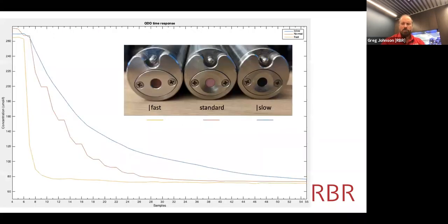Here is the photograph of the 3 foils. You can see in the center that opaque pink foil. Actually, the same foil is used for the slow instrument on the right-hand side, but it's covered in a black Teflon membrane. That allows us to wipe it without the wiper causing any damage to the porphyrin complex. And that's really what accounts for the time constant difference, is the amount of time that the oxygen takes to diffuse through the Teflon. That left-hand one is the transparent foil that I mentioned, which if you were to look carefully, you can actually see the electronics on the inside of the instrument through that foil.